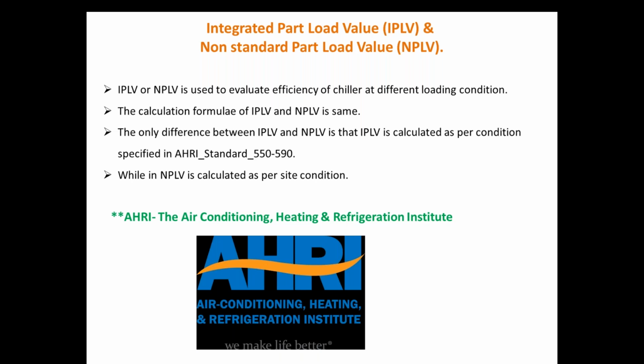The only difference between integrated part load value and non-standard part load value is, I think, the nomenclature itself is self-explanatory: IPLV is the integrated part load value, and NPLV is non-standard. IPLV is based on the standard as per AHRI standard 550-590. Clear? AHRI is the Air Conditioning, Heating and Refrigeration Institute, and standard 550-590 is given for this IPLV standardization. If you are evaluating your refrigerating device with respect to the standard, then the value obtained is called the IPLV.